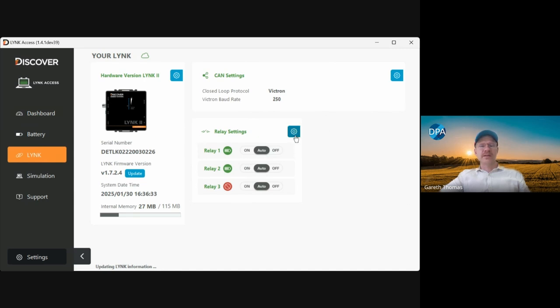Over here we have relay settings. The LYNK II has another great little feature you don't see anywhere else, which is it has these relays on the side of it. You can use them for things like configuring a generator, stopping and starting a generator. The reason that might be useful is it allows you to start up something based on the battery rather than based on the inverter. So in a black start scenario, instead of having the inverter start the generator, if the inverter loses its mind and stops functioning, the battery can start the generator and you'll still have power on site.